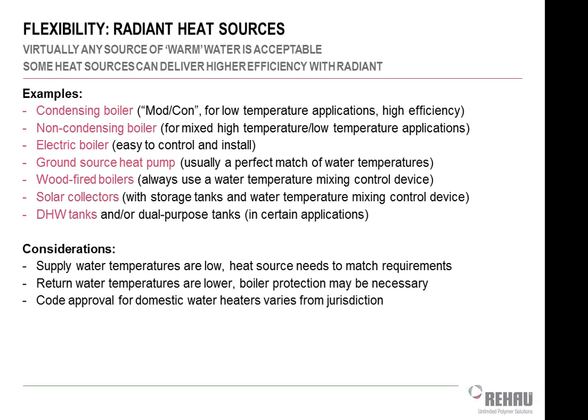But those water-to-water ground source heat pumps can very easily produce 115, 120, 125 degree water, so they're very well suited to use with a radiant heating system. And you can also tie them to any other type of radiant source as long as you have mixing control devices to keep the water temperature from getting too hot.